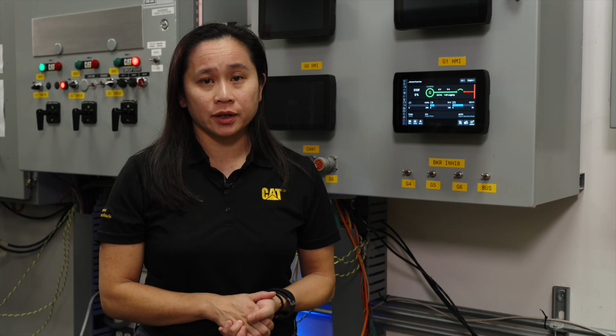One of the features I want to demonstrate for you today is AMF, Auto Mains Failure. For AMF, we have the utility power source providing power to the load, and we have the genset power. What you see on the HMI is the genset controller HMI screen. When the genset detects or senses a loss of utility, it will start up and close its breaker to support the load.